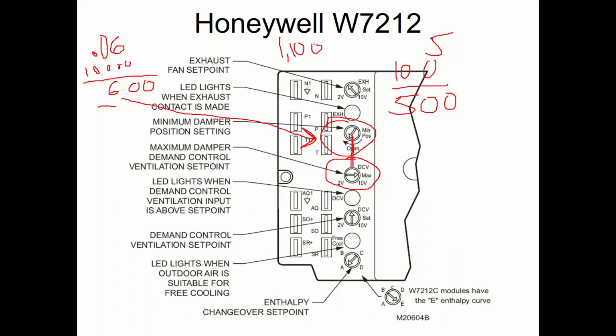And then because of the way these are labeled, it gets confusing. And people instead put the 1,100 on the minimum, and then they put something higher, typically 50% of damper position. I have no idea why they do that. They put 50% on there. And now this thing modulates between code minimum and something really high, instead of modulating between code minimum and something less. The new Jade controller doesn't do it this way. It's much more intuitive. So it's a lot better way to do it. But a lot of the existing systems have this.